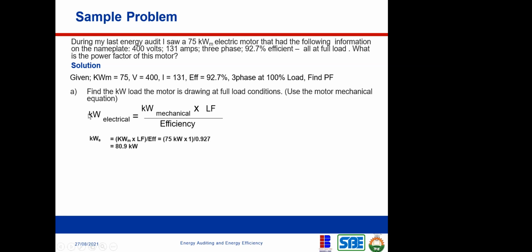Now this kilowatt electrical is equal to kilowatt mechanical times load factor all over efficiency. We know what the kilowatt mechanical is, we know what the load factor is, and we know what the efficiency is. So it's simple, we just put in the values. Our kilowatt mechanical is 75, our load factor is 100%, so it's 1, and our efficiency is 92.7%, so 0.927. Once you put that into this formula, we get 80.9 kilowatts electrical.